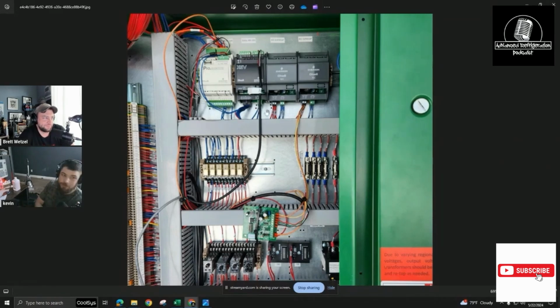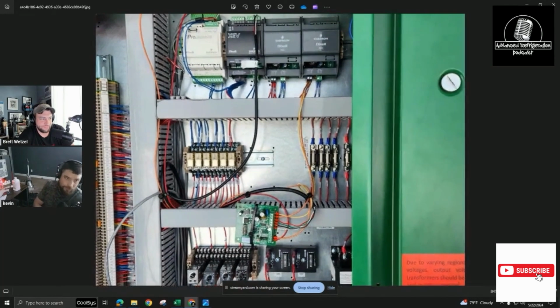I took a Sporlan IB board, and you could put 0 to 10 volts to it out of the iPro, which is nice because it has the ability to throw the 0 to 10 out, or the 4 to 20 milliamp, and drive an output to a valve. The only problem is it's made for Sporlan valves, so the steps are all off. So I had some figuring out to do.